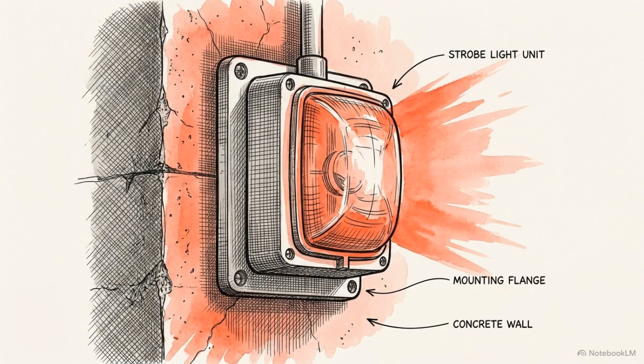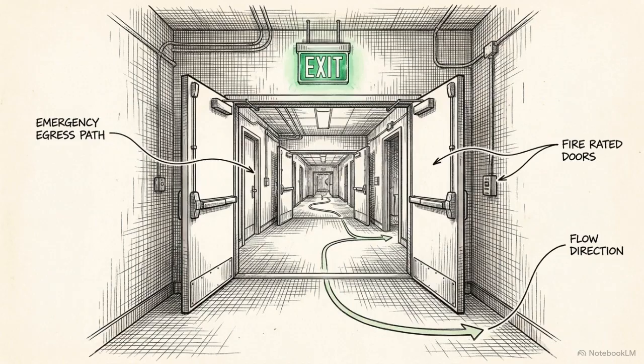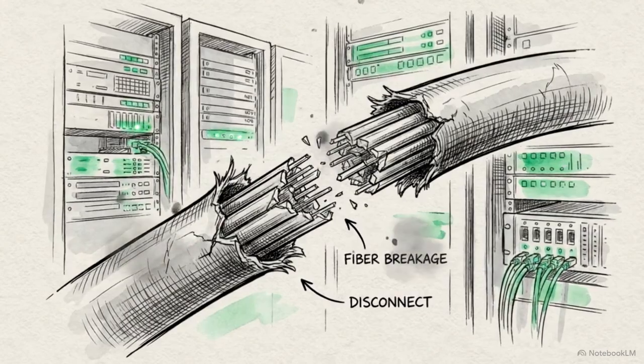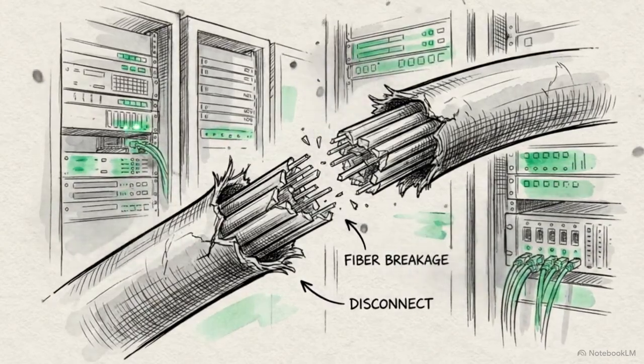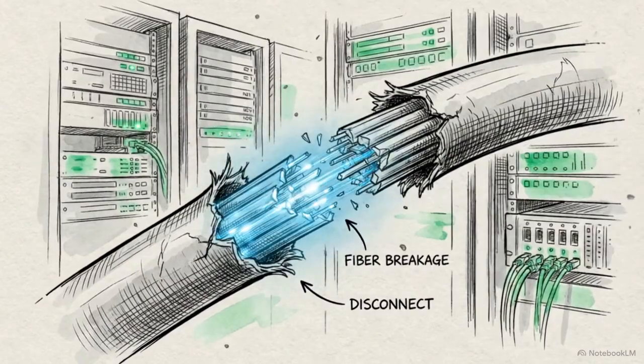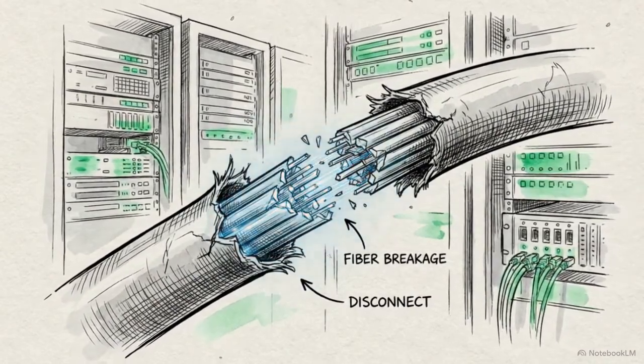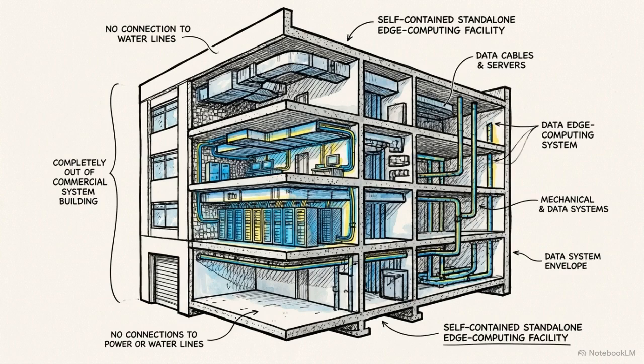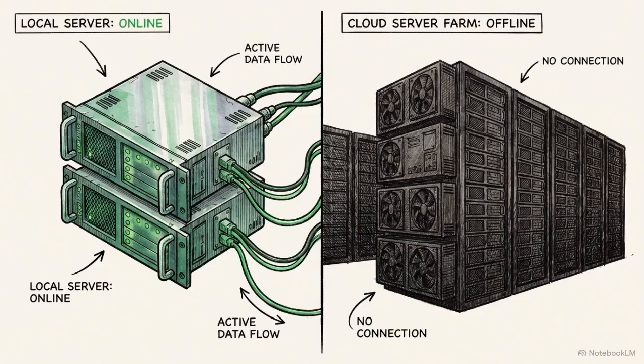If a fire system detects an alarm, the HVAC system must immediately stop pushing air to contain smoke, and the access control system must unlock emergency exits. If the building's internet connection fails, any cloud-based safety logic becomes completely inaccessible. The internal network must keep functioning in an isolated loop. This is a pure application of edge computing principles. By keeping the supervisory server on site, the building prioritizes operational continuity over centralized processing power. In critical infrastructure, continuity is the primary metric of success.